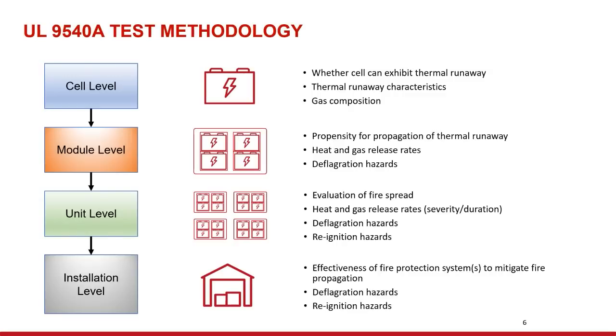If that failure had happened in an occupied building, it could have put someone at risk. So we developed a step process. First, we test at the cell level, and then we evaluate the thermal runaway characteristics and the gas composition and see what happens with the flaming once that fails. Then we would go to the module level. Again, we're evaluating for the propensity of propagation of runaway. We're evaluating the heat and gas release rates, and we're evaluating deflagration hazards.